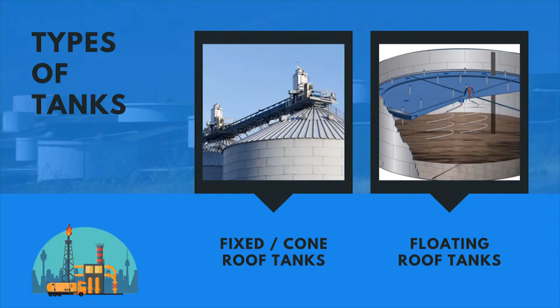To address the evaporation loss, designers came out with another type of tank known as the floating roof tank. Here, the roof floats on the surface of the liquid and is not tightly fixed or welded to the tank shell. So the roof can float up when the liquid level rises, and come down when it falls. This way there is no gap between the roof surface and the liquid surface, which minimizes evaporation.